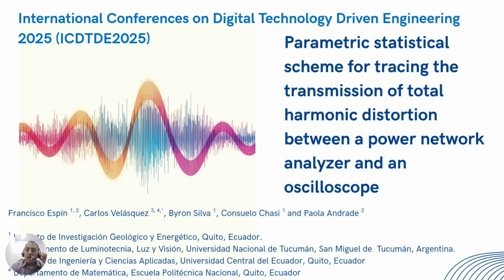Hello everybody, it is a pleasure to present our research titled Parametric Statistical Scheme for Tracing the Transmission of Total Harmonic Distortion between a Power Network Analyzer and an Oscilloscope. This work addresses a crucial methodological challenge in the field of power quality. The traceability of total harmonic distortion, or THD, measurement is fundamental for confidence in the results of any measurement. Through this presentation, we will explore a non-standardized methodology that allows the transfer of metrological traceability from a widely calibrated reference instrument to a power network analyzer.